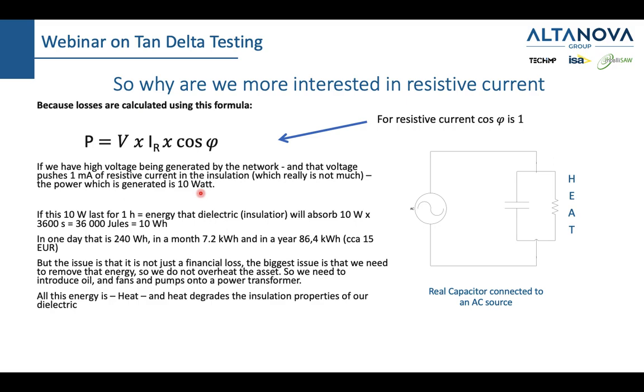watts. But 10 watt for 1 hour will dissipate 36,000 joules or 10 watt hours on the insulation of that transformer. Also, if that lasts for the whole day, we will dissipate 240 watt hours, in a month 7.2 kilowatt hours, and in a year 86.4 kilowatt hours. If we take the mean price of 1 kilowatt hour, we will lose about 15 euros per year on a small distribution transformer. But it's not the funds, it's not the money which is important here. It is the fact that all this power turns into heat.